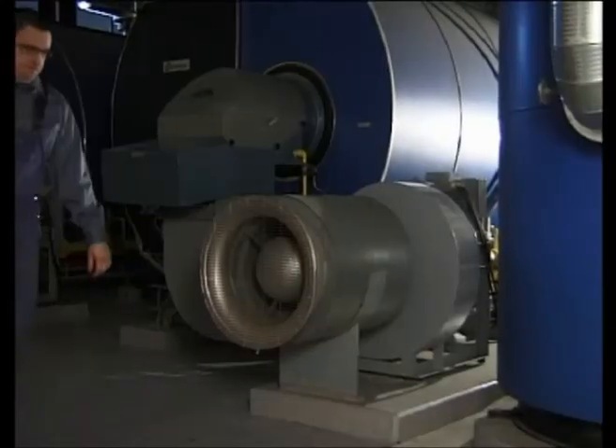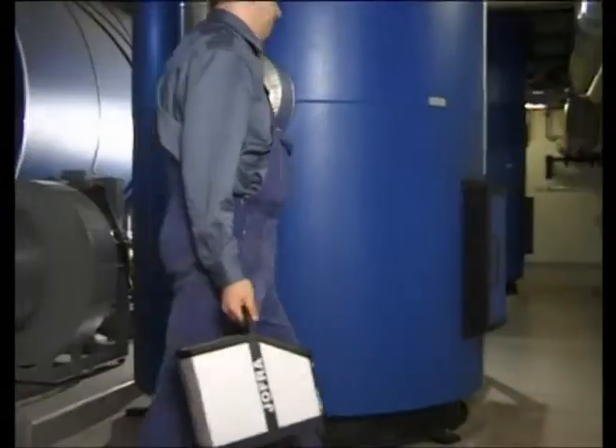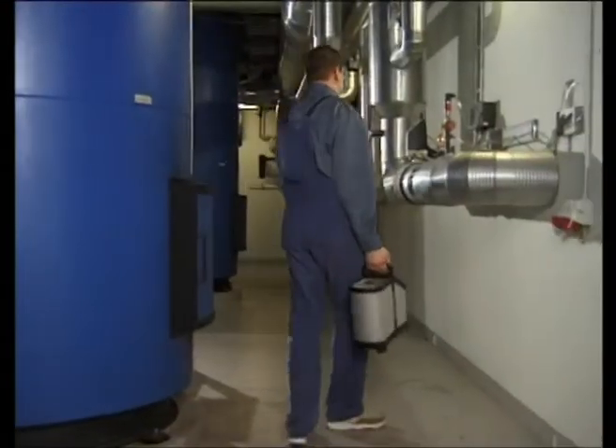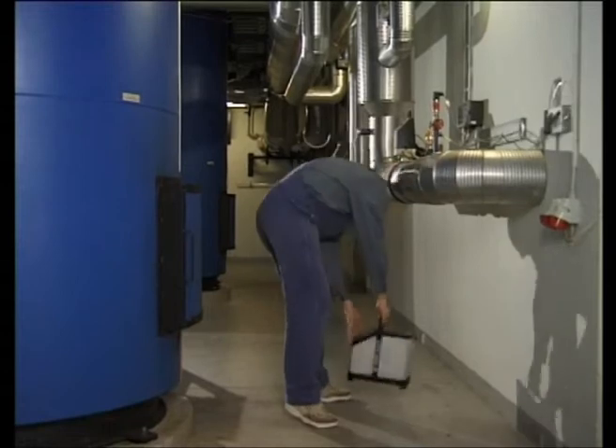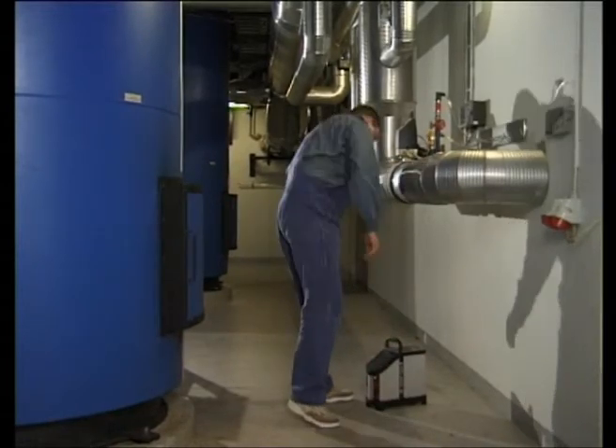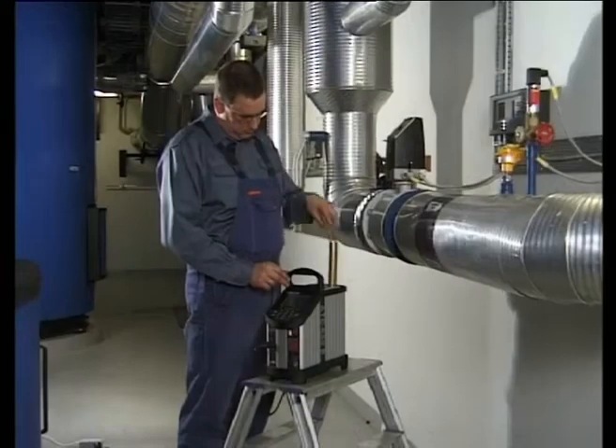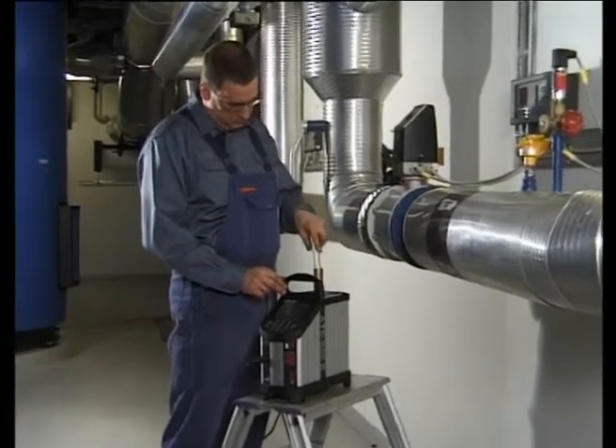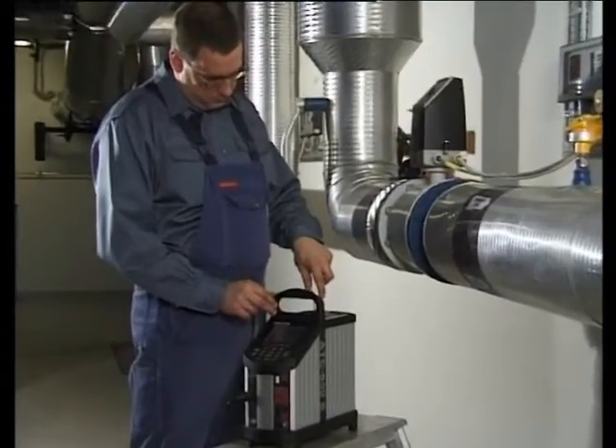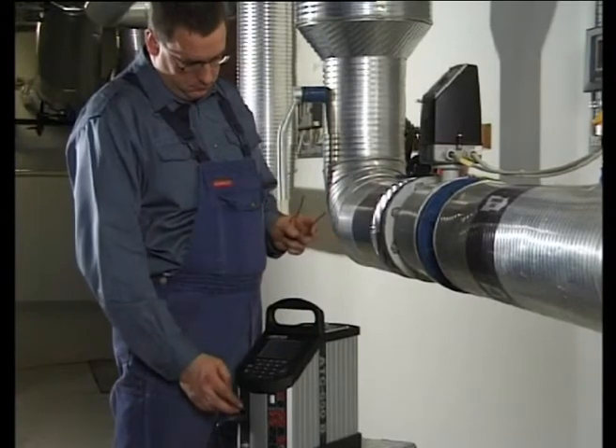The Jofra ATC series greatly improves your calibration results. Not only does this series have a built-in reference sensor in the well, it is also equipped with an external reference thermometer, thus enabling one instrument to provide you with the freedom to perform your calibrations at the process site while maintaining a higher level of accuracy.